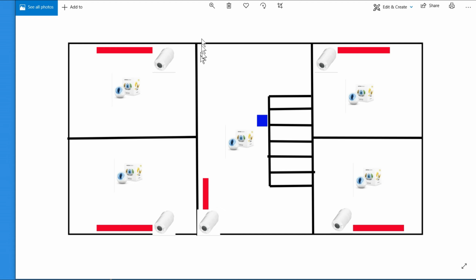The sun for us rises from the front but sets at the back of the house, so most of the day this side of the property is always a lot warmer than the front of the property. So we can offset the different set points by mimicking the same thing. We don't have to put a higher set point there, we just keep it lower. So the advantages are that we're able to control the set points individually for individual rooms, and it doesn't have to be just the example I've shown here with 5 zones. It can be as many zones, as many rooms as needed.